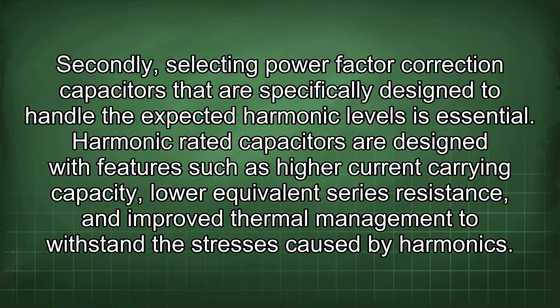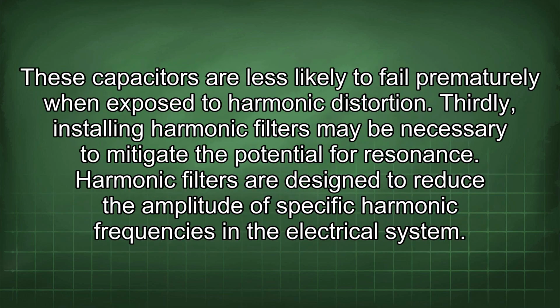Secondly, selecting power factor correction capacitors that are specifically designed to handle the expected harmonic levels is essential. Harmonic-rated capacitors are designed with features such as higher current carrying capacity, lower equivalent series resistance, and improved thermal management to withstand the stresses caused by harmonics. These capacitors are less likely to fail prematurely when exposed to harmonic distortion. Thirdly, installing harmonic filters may be necessary to mitigate the potential for resonance. Harmonic filters are designed to reduce the amplitude of specific harmonic frequencies in the electrical system.